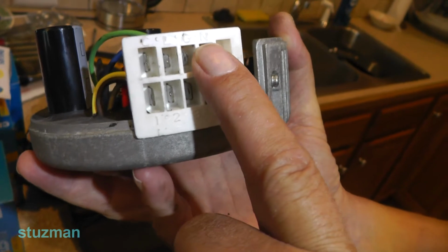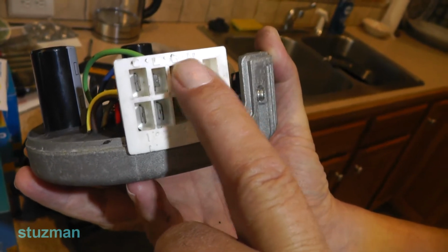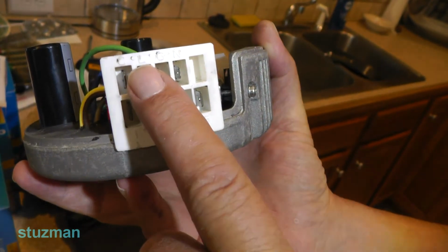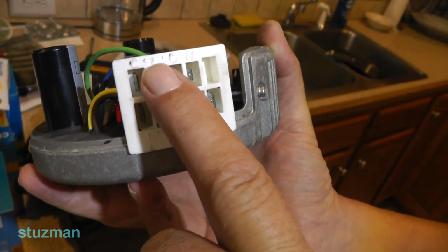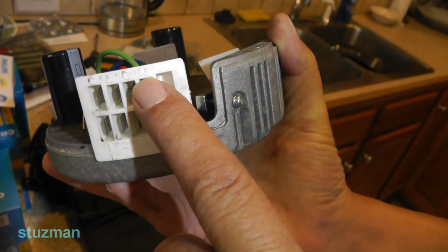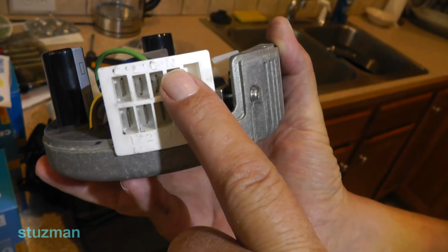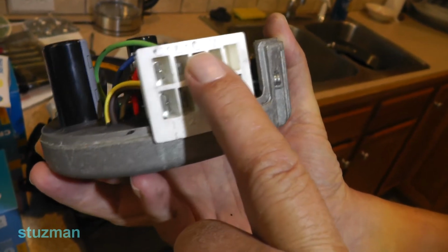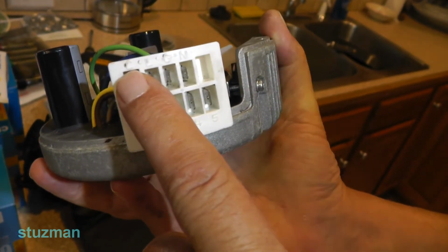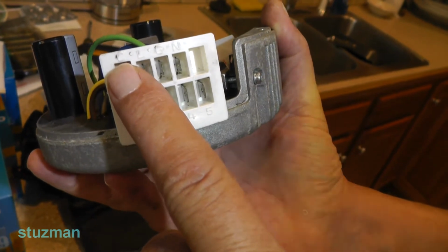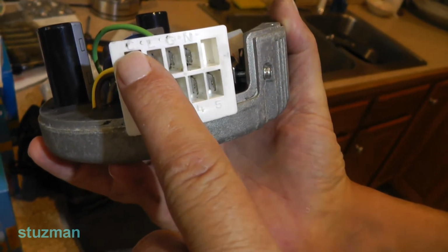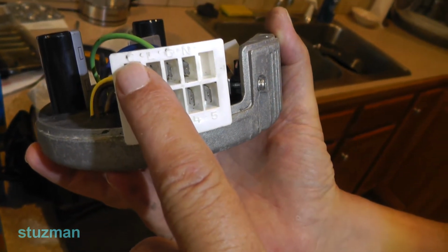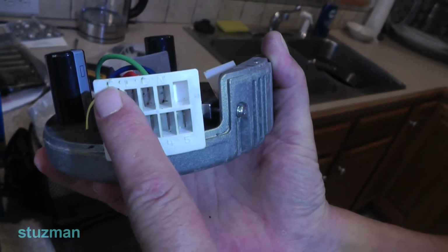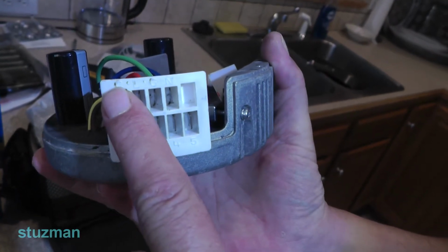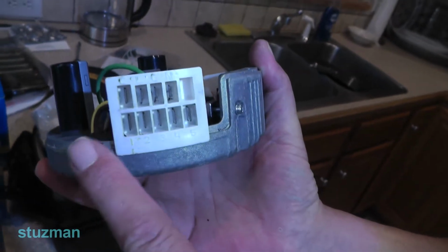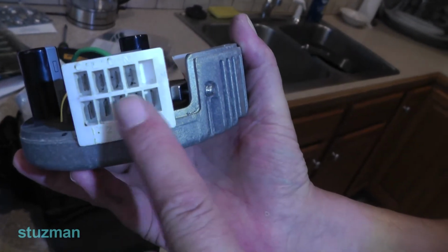So of course your line power is going to be between the N and the L. If it's 240 volts, like in my case, then it's going to be L and N that are used for the two hot wires. Of course the G is equipment ground, and if you look right over here, you can see C, which is common. Common is for the communication line. That's one side of the 24 volt AC. You're going to use that in no matter what case for your communication taps. Now your taps can be 1, 2, 3, 4, or 5.